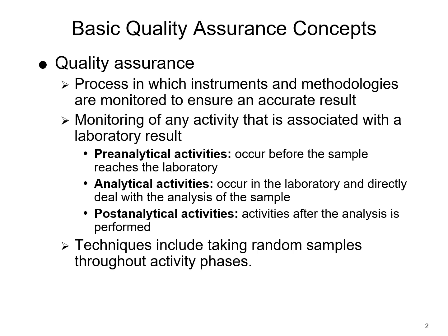Now, an example of an analytical activity would be something that happened while you were testing. Maybe there was a bubble that was sucked up into the analyzer, so it gave you a false result. Maybe QC failed for the day. Maybe there's some kind of error in the room, like the temperature has gotten too high. Maybe there was a power failure while that sample was running through. These could all be issues that happen while the testing is actually taking place.